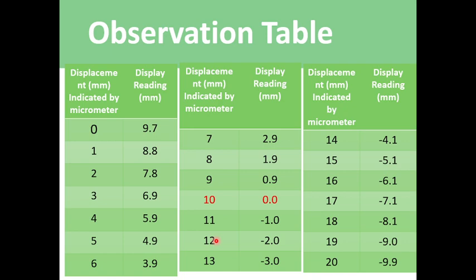If we go anti-clockwise and rotate the thimble beyond 10, to 11, 12, 13, 14, it simply gives negative values. This results from the fact that the induced EMF at secondary coil 2 now increases while the induced EMF at secondary coil 1 decreases, and at the extreme point the EMF due to secondary coil 2 is maximum while secondary coil 1 is lowest, but not 0.